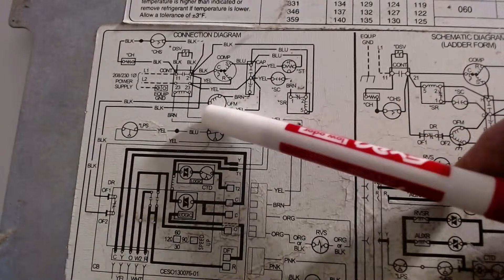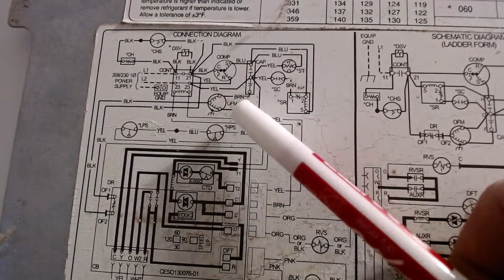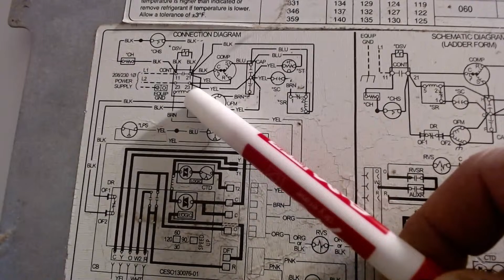Now what some people don't realize, and you can do it, and they're like, you can't do that, that's not right - this wire right here, coming off of your fan motor, going to common of the capacitor, can also come off of here and go straight to the 23 terminal. They're using the capacitor as a junction point for that terminal, that's all they're doing. This can go over there. So if you don't want to put it there, or it's tight and you can reach back over here, go ahead. But that's how the schematic is drawn.